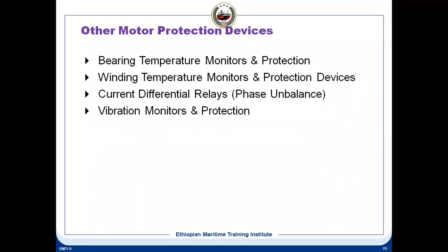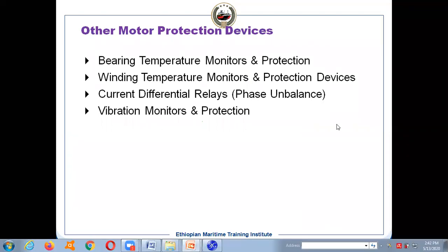The other protections are bearing temperature monitors, winding temperatures, current differential relays, phase balance, and vibration monitors. The bearing temperature monitors can be RTDs, which sense the bearing temperature, and whenever the temperature exceeds the limits, it gives a warning alarm. For winding temperatures, we use thermistors. Thermistors generally can go up to 200 degrees centigrade.